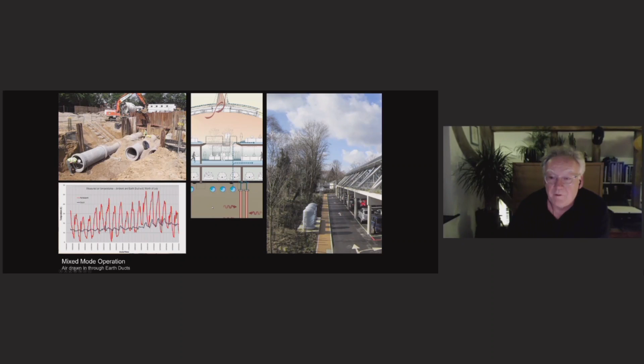The other thermal mass system on the project is these earth energy piles. So we've got about 42 100-meter, 300-foot deep closed loop piles. These are the pipes being pushed down into the piles, and we basically run a water glycol mix through them, and we run a heat pump so that we use the ground as our energy store. And because the ground is always at around 12 degrees centigrade, we can be really efficient taking heat out and pushing any cooling back into it. So there's lots of earth contact in all that.